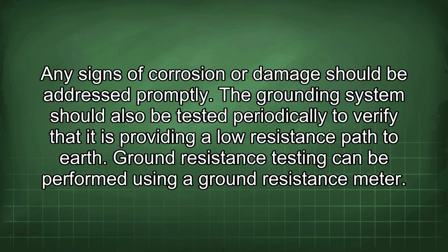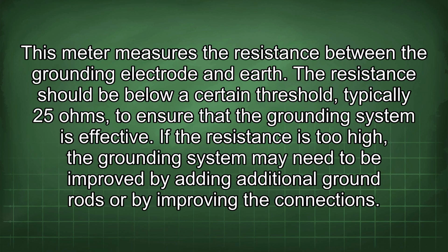Ground resistance testing can be performed using a ground resistance meter. This meter measures the resistance between the grounding electrode and earth. The resistance should be below a certain threshold, typically 25 ohms, to ensure that the grounding system is effective. If the resistance is too high, the grounding system may need to be improved by adding additional ground rods or by improving the connections.